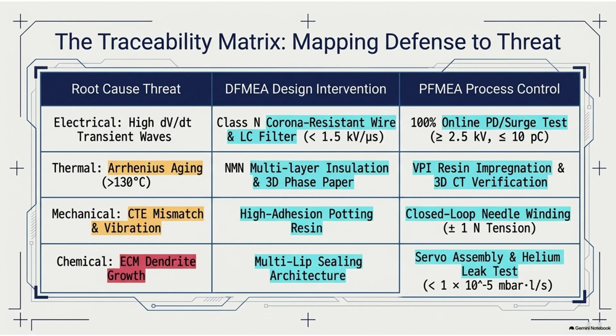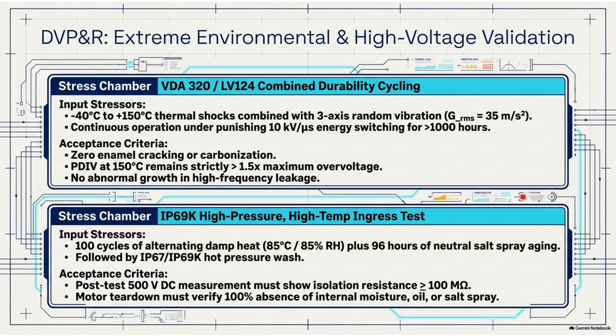And the craziest part is they don't even trust that process completely. The source states they use a 3D industrial CT scanner, like a medical CT scan, to physically look inside the solid metal and resin to prove there are absolutely zero voids. Because if a void exists, the motor is useless. Okay. And to verify the electrical integrity on the assembly line, they mandate a 100% online PD and surge test. Right. They hook up this freshly built motor and blast it with over 2,500 volts of electricity right there in the factory. Yeah. They're intentionally trying to break it.